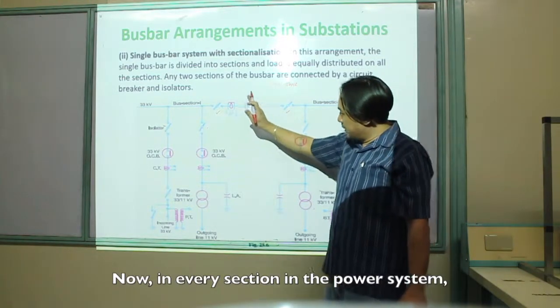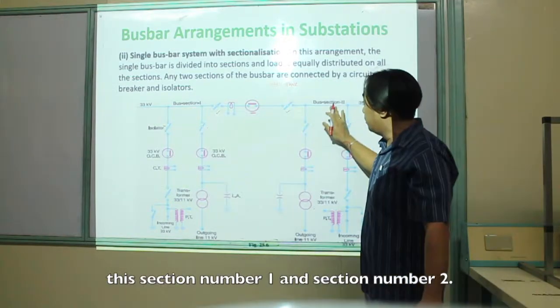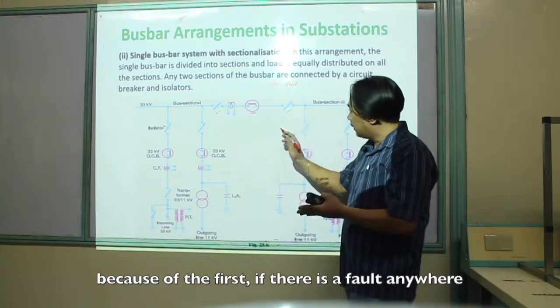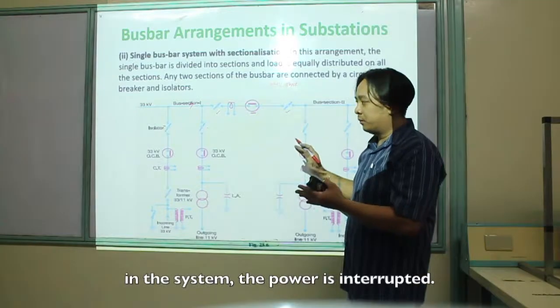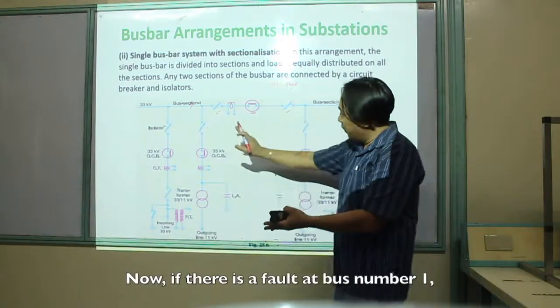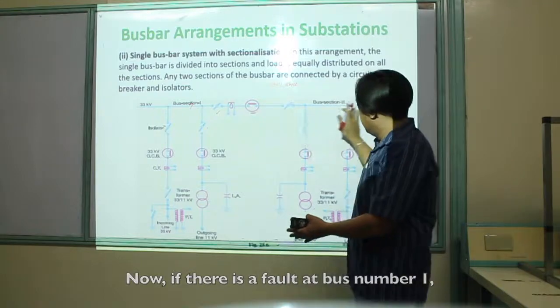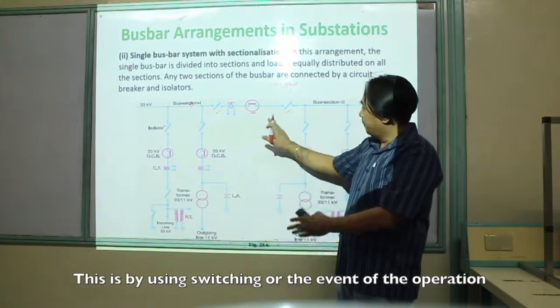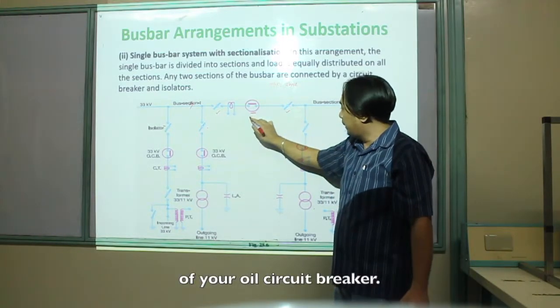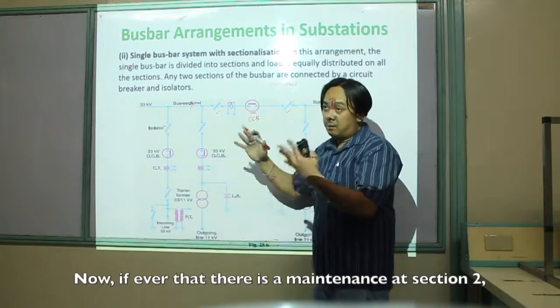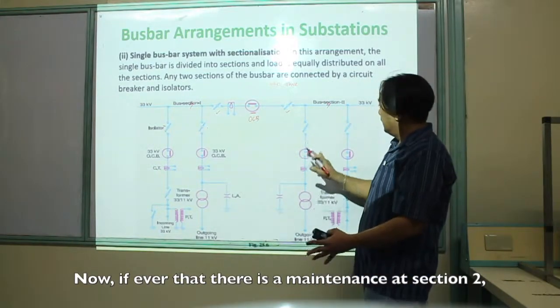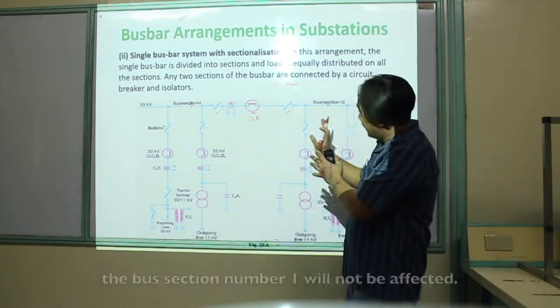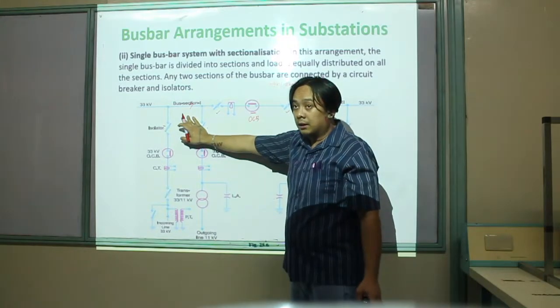In every section of the power system — section one and section two — this is compensated from the first arrangement. On the first type, if there is a fault anywhere, the power is interrupted. Now, if there is a fault at bus section number one, bus section number two will not be affected. Similarly, if there is maintenance at section number two, bus section number one will not be affected.